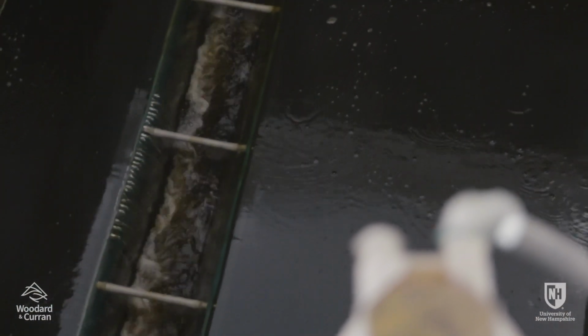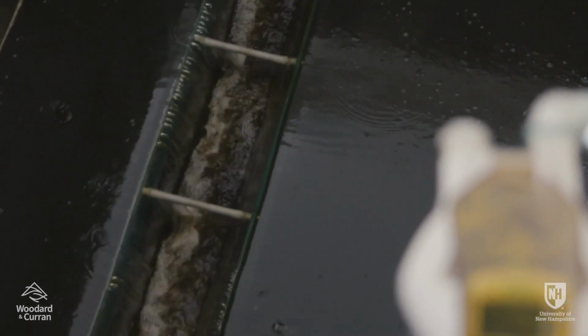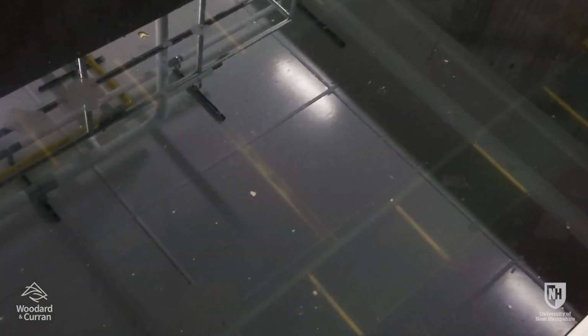Backwash waste is directed to the same lagoon as the clarifier waste. After a backwash and before a filter is brought back online, the process called filter to waste is performed. Clarified water flows through the filter for a short period of time and is directed to the lagoons instead of through the remaining treatment steps. This allows the filter media to resettle and ensures optimal filter performance.